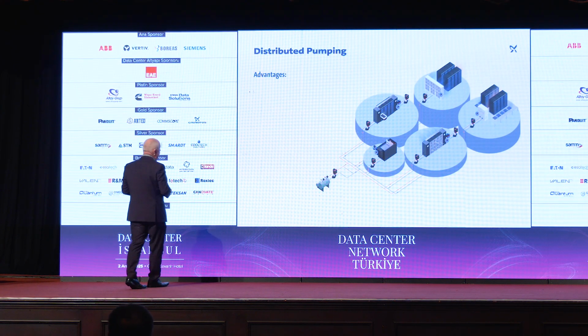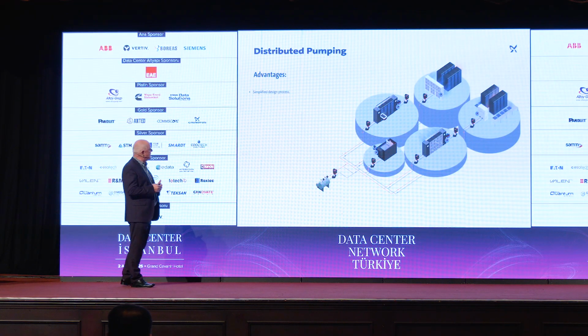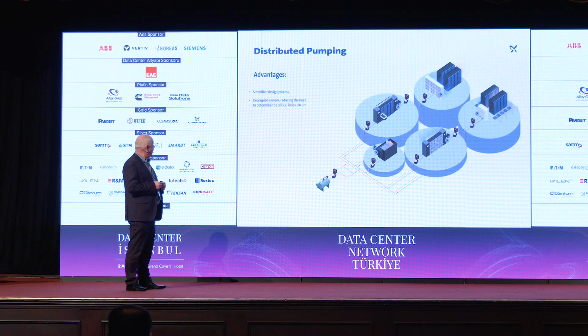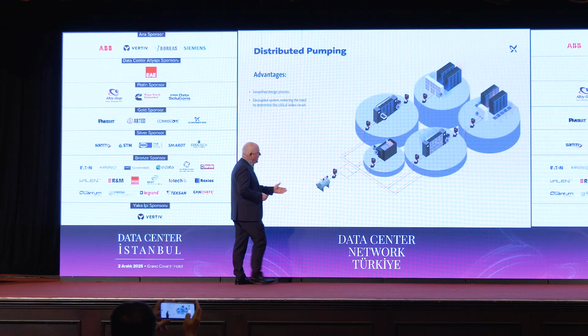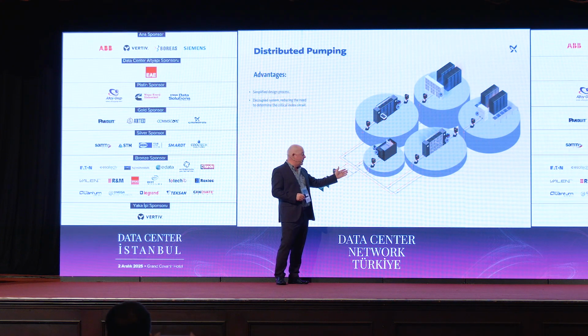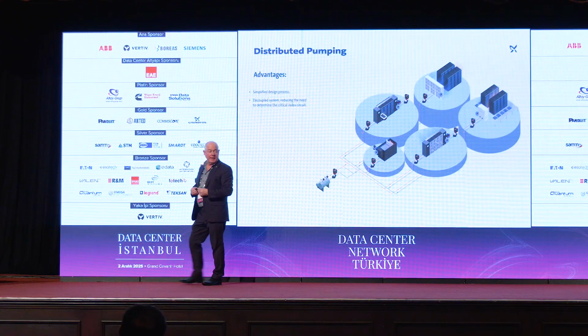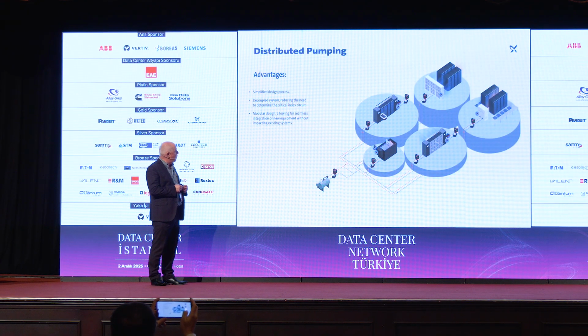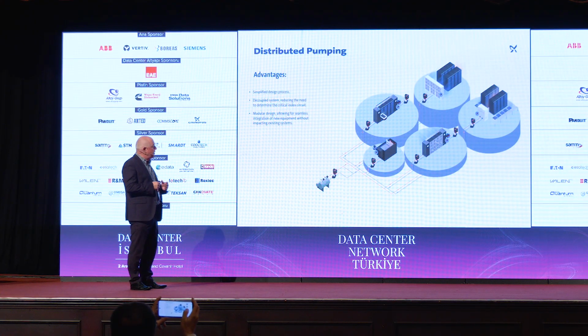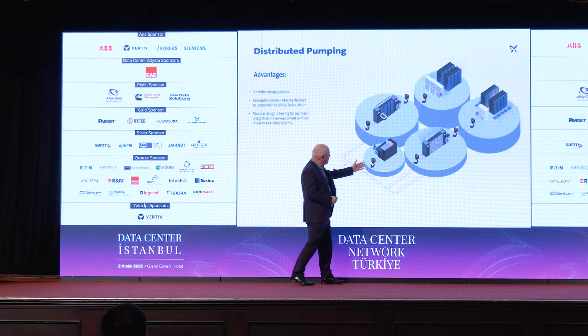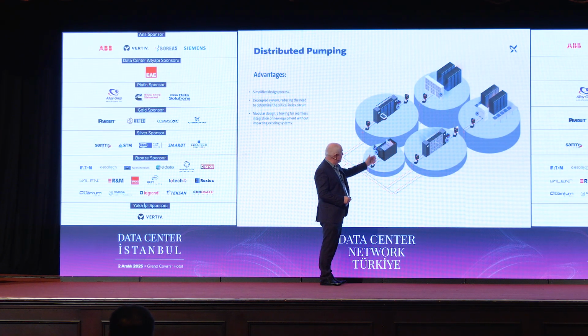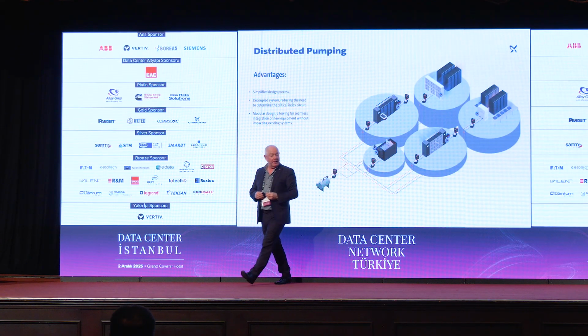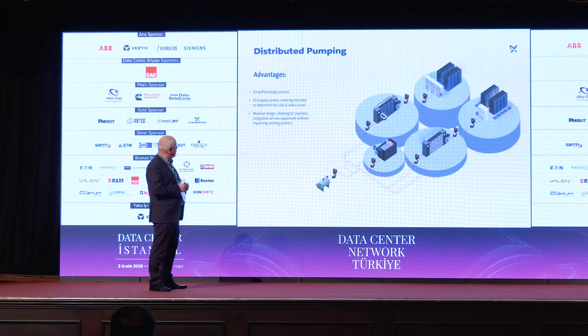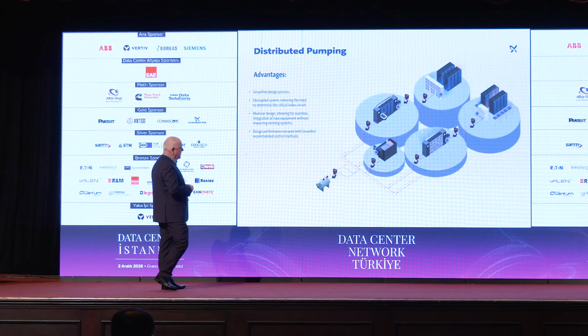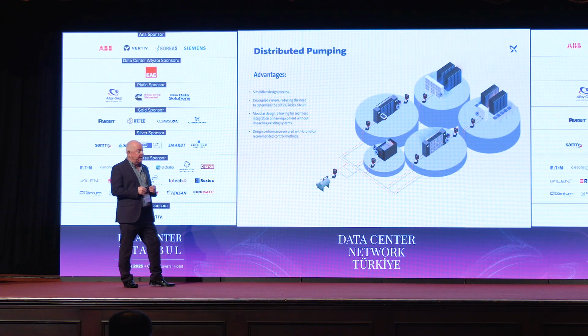So if we look at distributed pumping and how we organize the system, it's a more simplified design process. We decouple. So we use the decoupling line here between the primary and the secondary, which is really, really important. We would like to have no flow in this decoupling line all the time, but there are times when we do. It lends itself very much to modular design because we're putting pumps at the point of application. So if we want to put another cooling load in, we just put another set of pumps in with it. And it makes it very, very easy to balance. And we get very involved in the whole design of this system. So we will work with designers, end users, installers to make sure that it's designed to meet the needs.